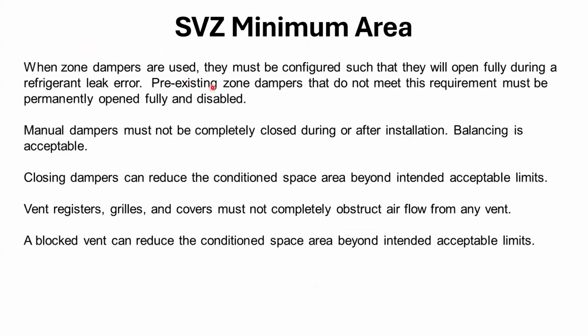When zone dampers are used, they must be configured such that they will open fully during a refrigerant leak. So if you have any type of zoning on the system, pre-existing zone dampers that do not meet this requirement need to be permanently opened, fully disabled, right? We have some more information coming up on what the system does, but we go high-speed fan for ventilating the room in case of a refrigerant leak. And if we have closed dampers, that's not going to ventilate the room, right? So that's what they're getting at right here.